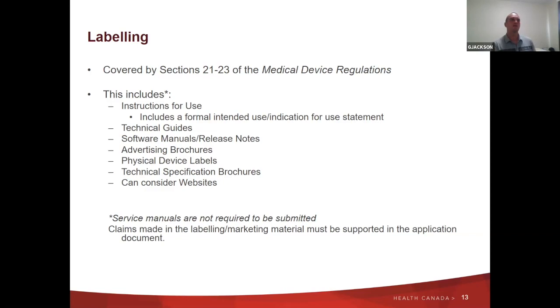We want to see that intended use or indications for use are present, unless it's self-evident to the user. Some intended uses can be pretty general. A CT scanner may say the intended use is to perform CT scans of patients, whereas for an ultrasound, for example, we'll have something like this individual probe is used for abdominal scans only when connected to this device. So it can get very specific or very general depending on what's required.